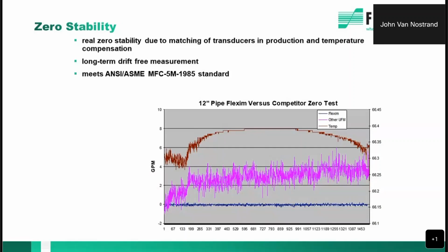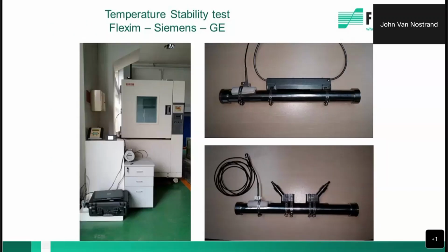And what you're seeing here is an overnight test of the blue line showing the zero output from the FLEXIM meter. The magenta line is the output from a competitor's meter, and the brown line is the temperature change over the test. And we're only looking at about maybe a degree or two of change, but look at the output from the competitor's meter versus the FLEXIM meter. So we took that a little bit further, and we just decided that we're going to do some laboratory testing.